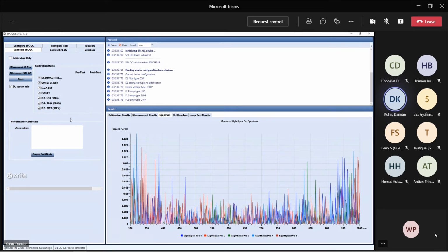If, due to whatever reason, you do not want to show pre-test values, maybe because you replaced the main board and there are no previous calibration values for the lamp voltages stored anyway on the new board, then you could activate that checkbox, and it will skip taking pre-test readings and directly start to adjust lamp voltages, only recording the performance after the lamp voltages were set and the light sources were calibrated.